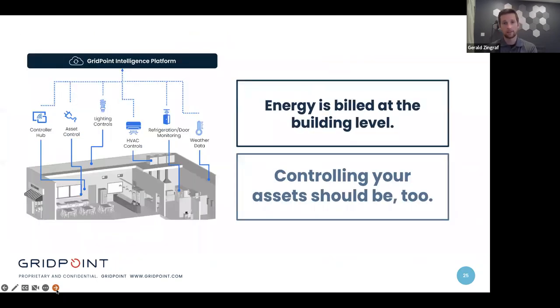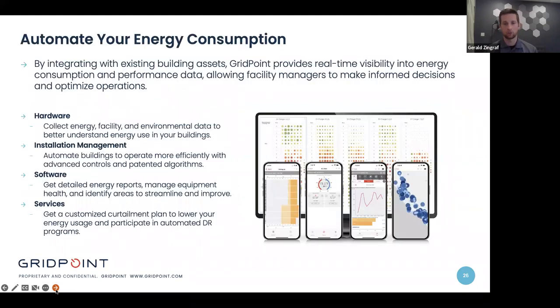So when you control everything as a system, it allows us to really be the conductor of an orchestra. We can tell HVAC to turn on at certain points and then lighting to throttle at certain points. And as we see that an EV charger or refrigeration compressor is going through, or the refrigeration unit is going through a defrost cycle, we can use these different sensors and the controls that we're doing at a site to start balancing the load, because your energy bill isn't billed based on how much your HVAC is consuming at any given point. You're billed at a building level. And all of these assets are contributing to your energy usage at a building level. So you need something that is considering all of these assets and how they're consuming energy throughout the day and how your tariff is structured. And are you on a time of use rate, or do you get billed for peak demand or demand charges? All of that contributes to our control strategy from a building perspective. So you really need something that can control it all together.